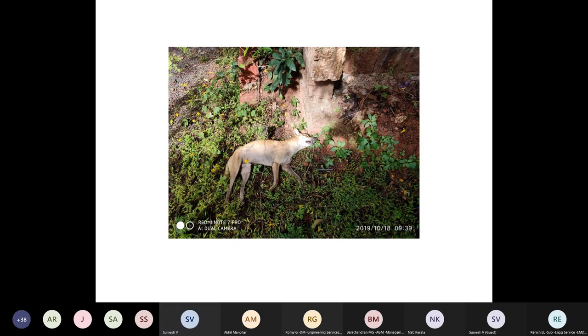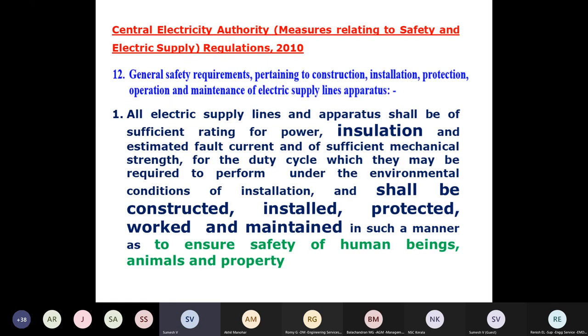Now we see a photo in which a fox has died, and you can see an electric earth wire in its mouth. Before that, we see a regulatory requirement. Regulation 12 of the Central Electricity Authority Safety Regulations says that all electric supply lines and apparatus shall be of sufficient rating for power, insulation and estimated fault current, and of sufficient mechanical strength for the duty cycle which they may require to perform under the environmental conditions of installation, and shall be constructed, installed, protected, worked and maintained in such a manner as to ensure safety of human beings, animals and property. This is the regulatory requirement.